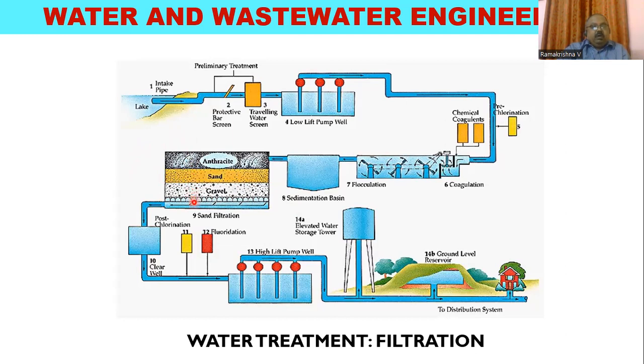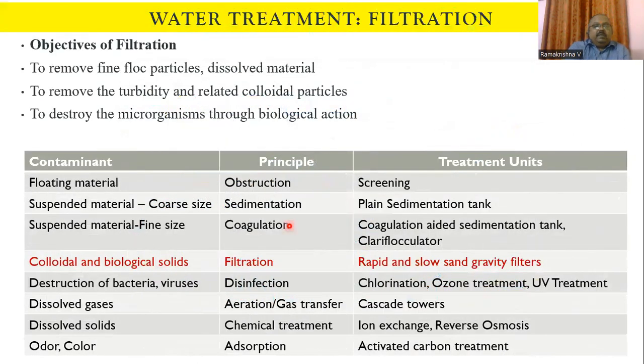The water passes through the strainer and enters what we call the underdrain pipes, then exits from the bottom. Sometimes a single filter medium is used, called a single sand filter. Other times more than one filter bed is used within the same filter, which we call dual media or multimedia filters.